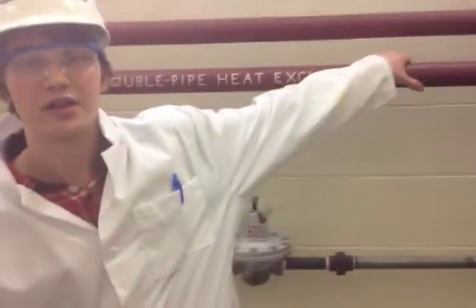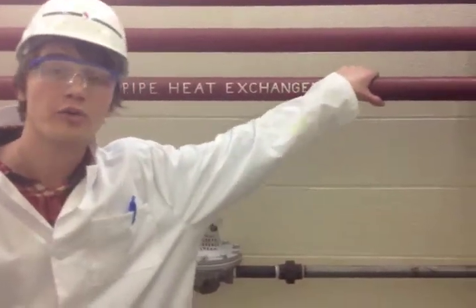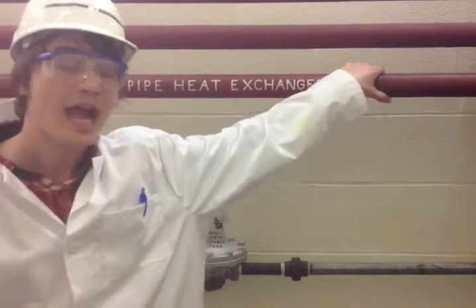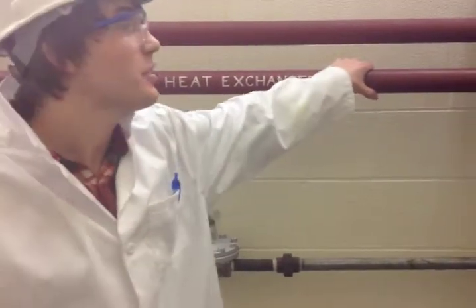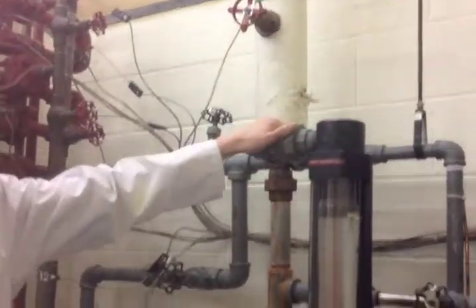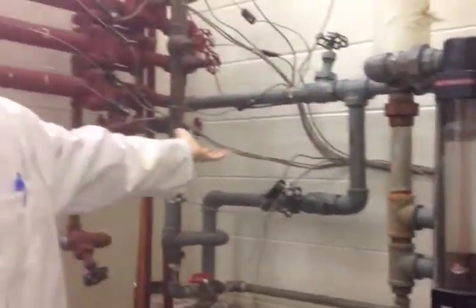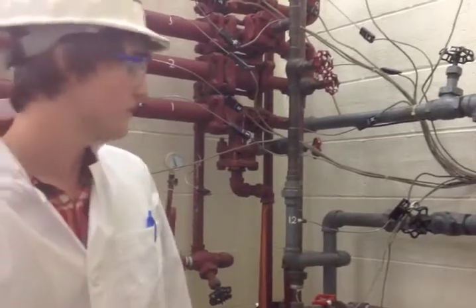This will still be very hot inside the shell and tube, and it will still be very hot in the double pipe, so you need to let the cold water run for an additional 5 minutes. After those 5 minutes have passed, you can come back over, close your cold main line, and close every valve that you use. So typically everything is closed when we're done with the system.